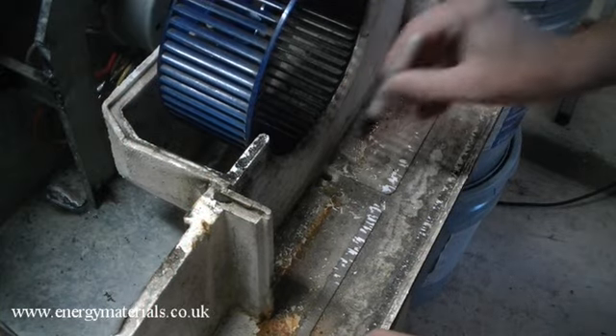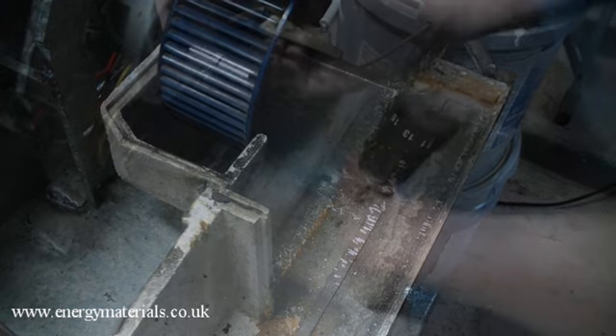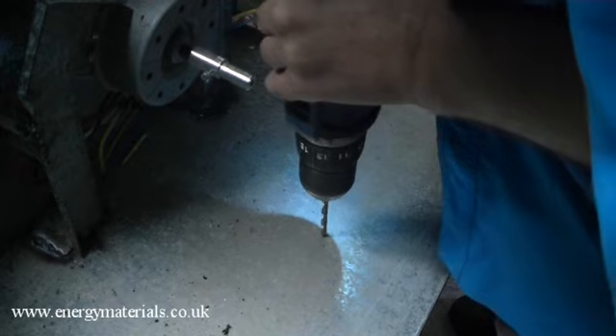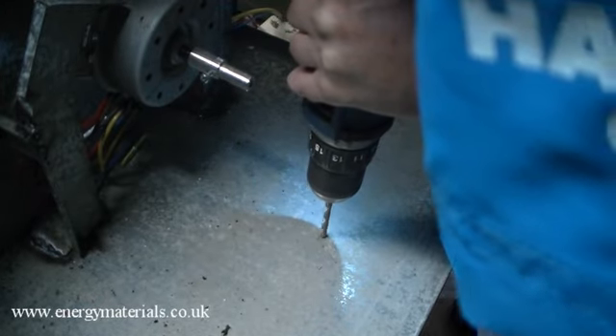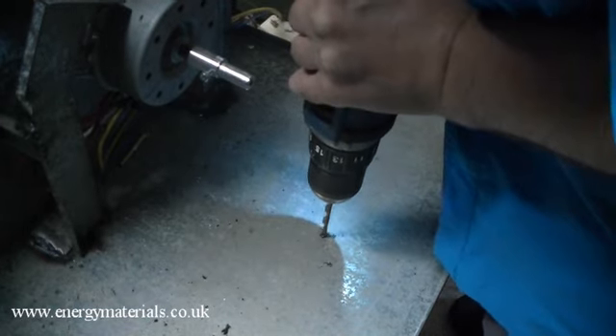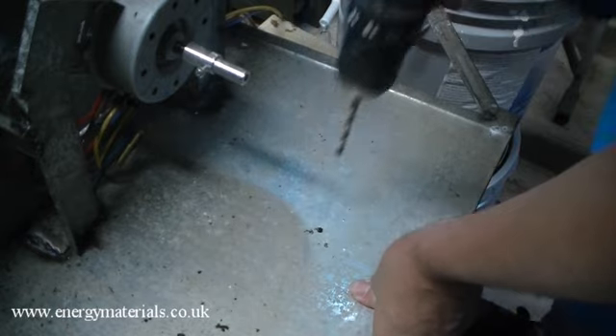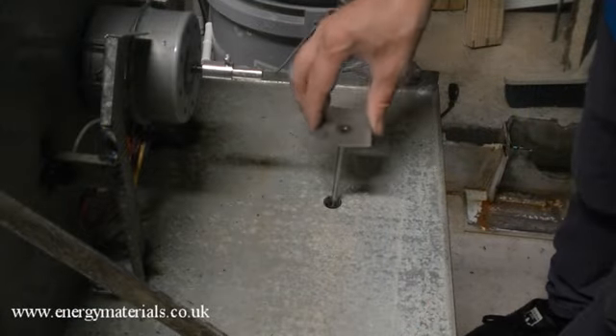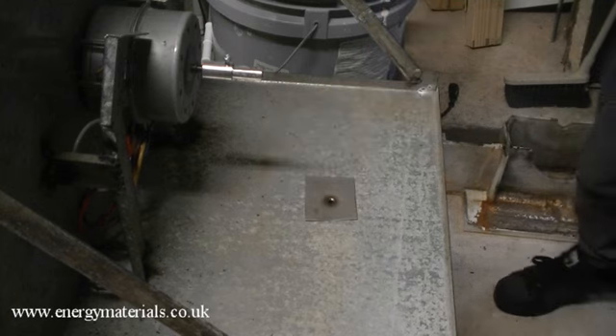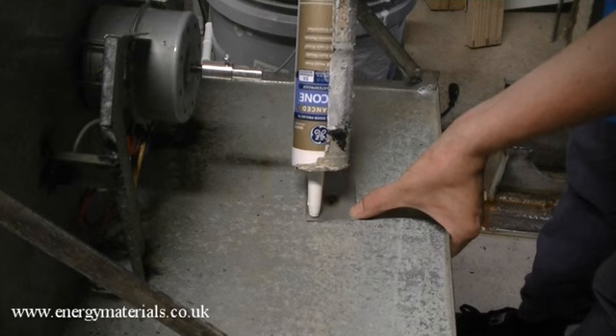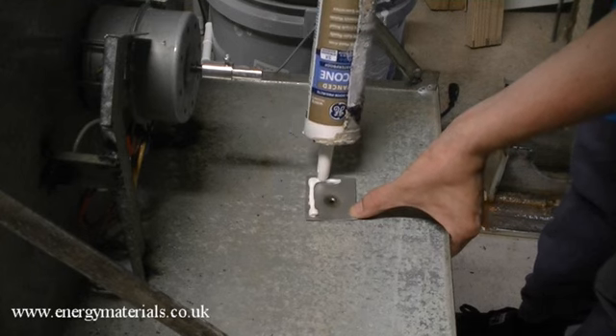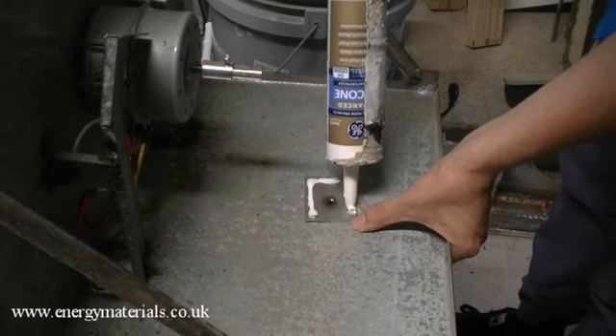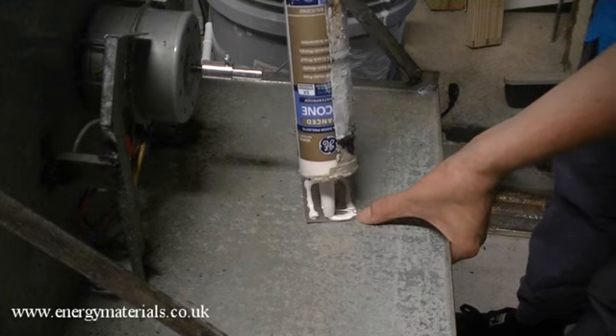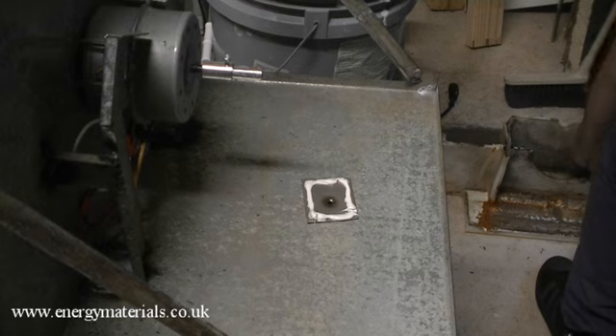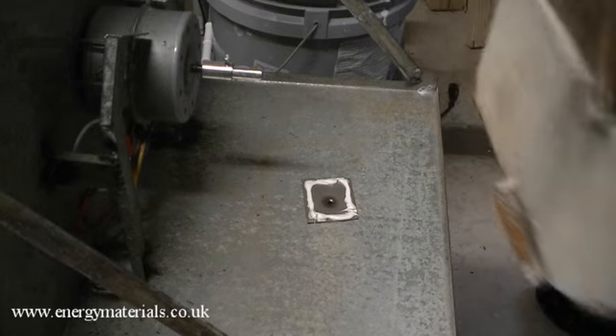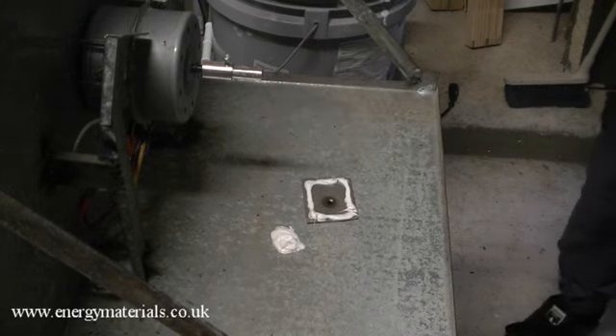So to install the condensate drain, we're going to mark out where the hole needs to be using a Sharpie. Now we're going to remove the radial fan and the lower cowling using a drill. We're going to drill a hole. Now with the hole drilled, we're going to test fit our drain line, and we're going to apply some silicone sealant to seal around our drain line on the top where it's going to meet with the cowling. And we're also going to put a blob of silicone sealant to help secure the cowling in a constant position within the frame that we've built.